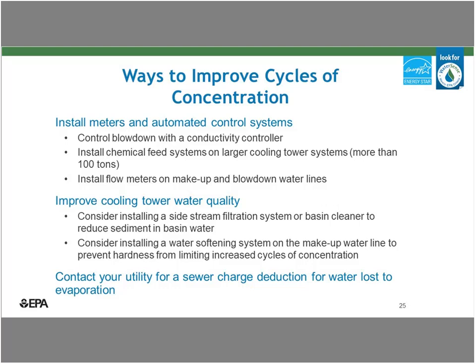Taking steps to improve your water quality, such as side stream filtration or basin cleaning to remove sediment, or even water softening if the incoming water hardness is a problem in your area, can also allow you to increase your cycles of concentration. Your water treatment vendor should be able to advise you on these options. And again, if they aren't offering these options, be sure to ask.